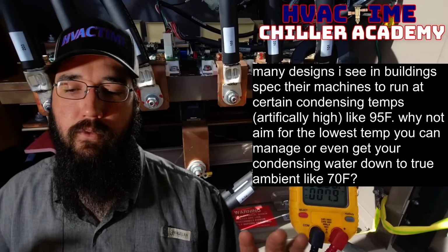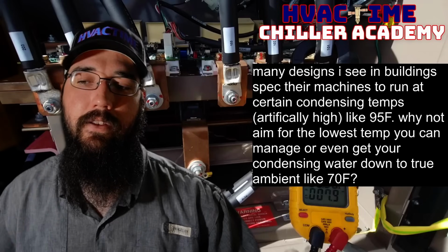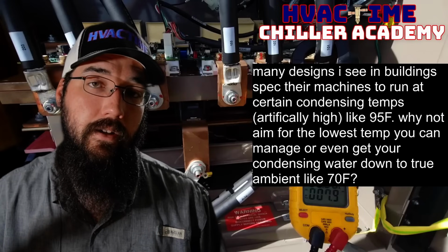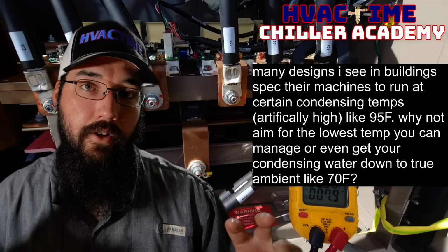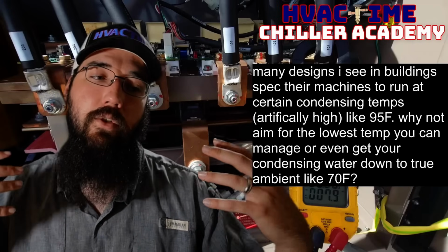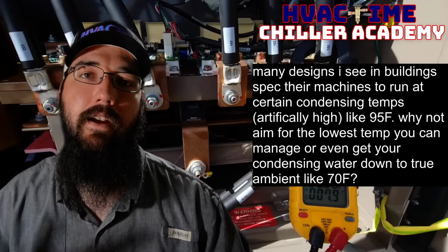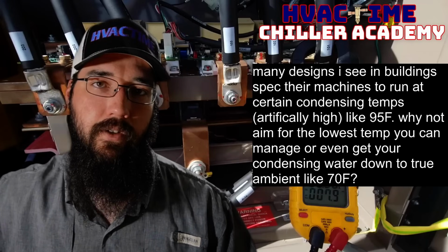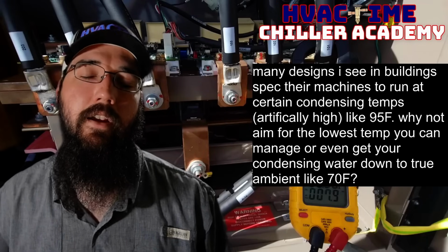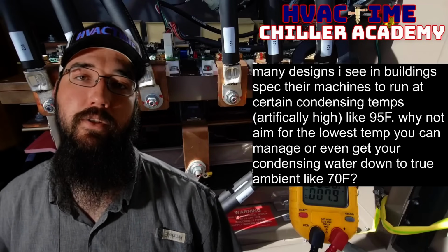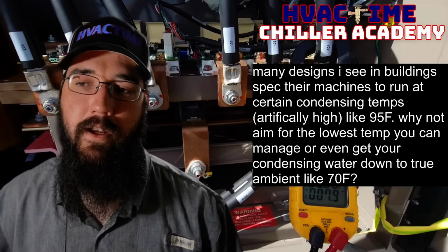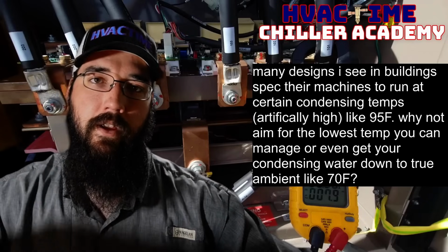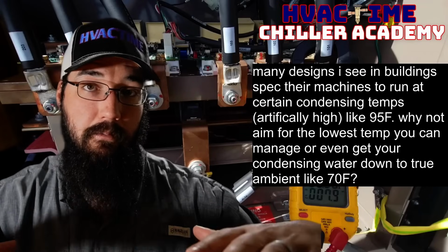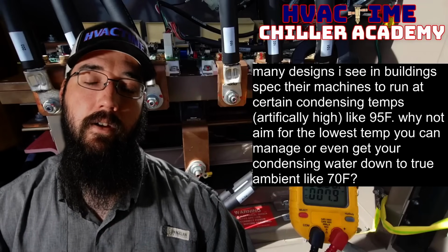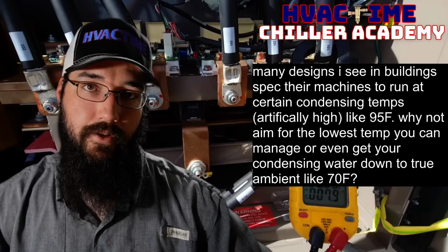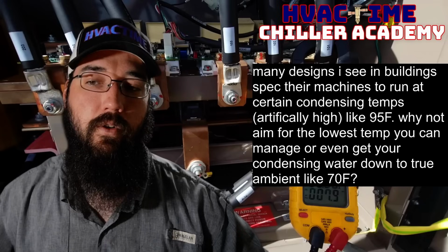And what ends up happening that I have seen is they'll do these things and they will end up showing where they've reduced the total energy usage of the building. And so they have this positive feedback loop to think that, okay, well, by setting that high condenser water set point, that was part of the bigger picture to take the load off, and we're now more efficient because of that. When in reality it's all the other things that they changed to help that building operate better that did lower the energy profile, but they did end up increasing the chiller's energy profile because of that condenser water set point.